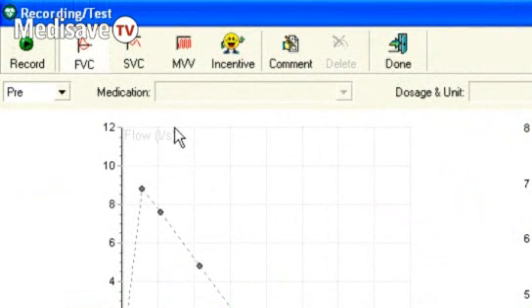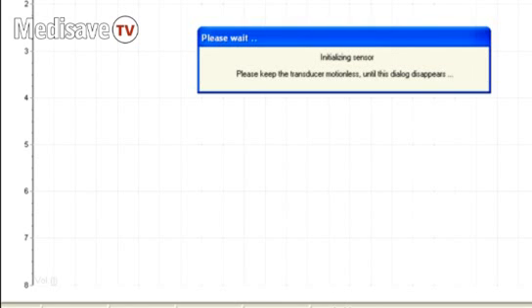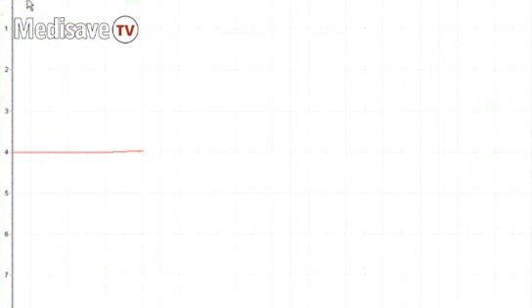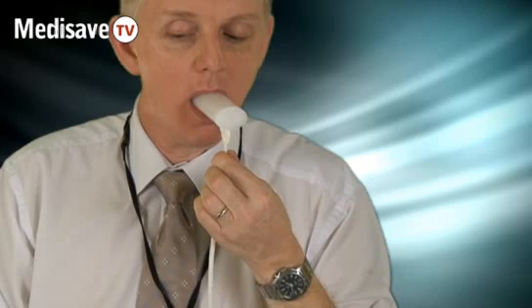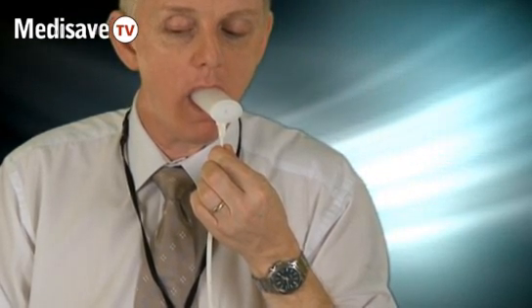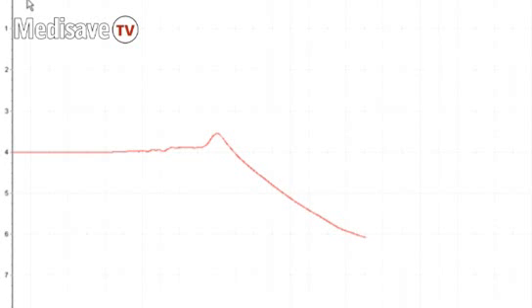When you're doing a spirometry test in the first instance, you should give the patient a relaxed vital capacity test first of all to get an idea of their lung capacity without any pressure. So when they're ready to take this, you click Record. When you see the test is ready to start, the patient can pick the mouthpiece up and gently blow into it. As you can see, their effort is measured on the PC screen. When they can't blow anymore, you press Stop.